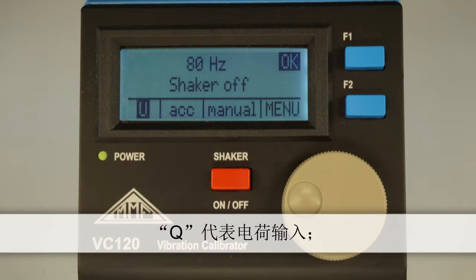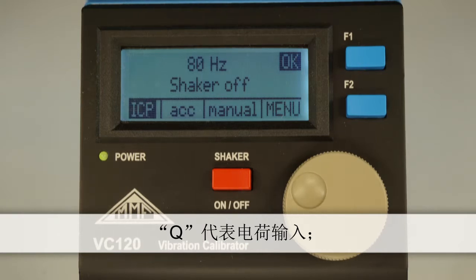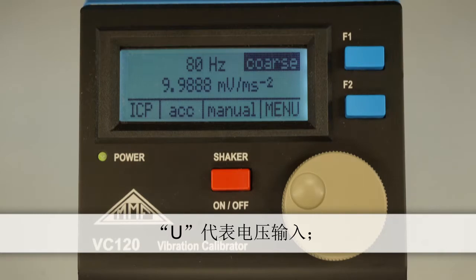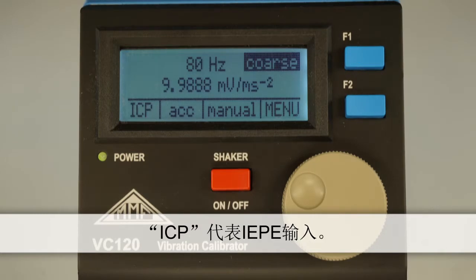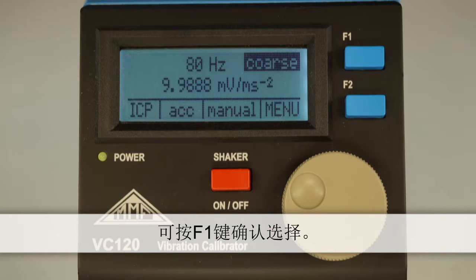Q for charge, U for voltage or ICP for IEPE. We want to calibrate an IEPE sensor and press F1 to confirm our choice.